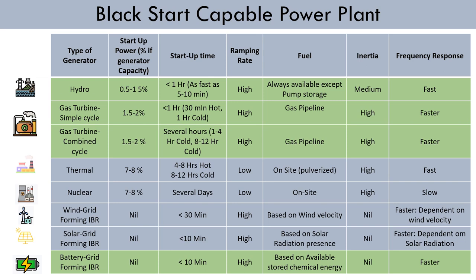Thermal and nuclear power plants are typically not considered suitable for black start capability due to various reasons. Firstly, they have longer startup times compared to other types of power plants, requiring extensive preparation and system checks before electricity generation can begin. Additionally, thermal and nuclear power plants often have slower ramp rates, meaning they are slower to adjust power output in response to sudden changes in demand or grid conditions. The complexity and safety considerations associated with these plants pose challenges in coordinating their startup with the synchronization of the entire power system during black start operations.